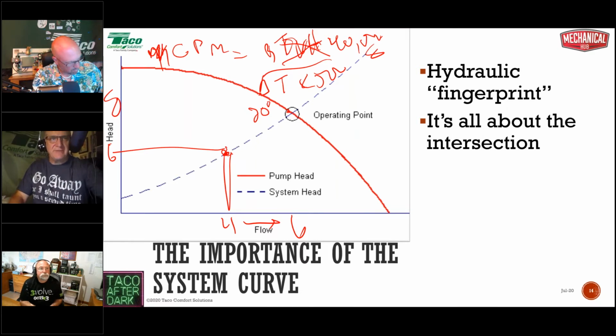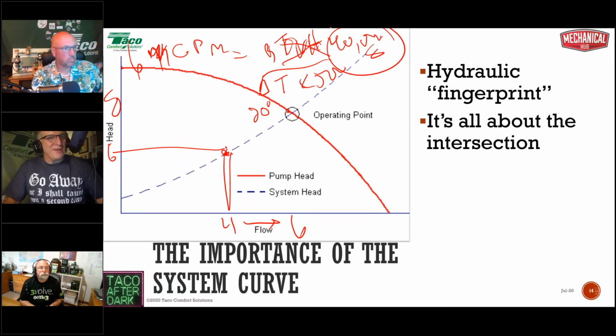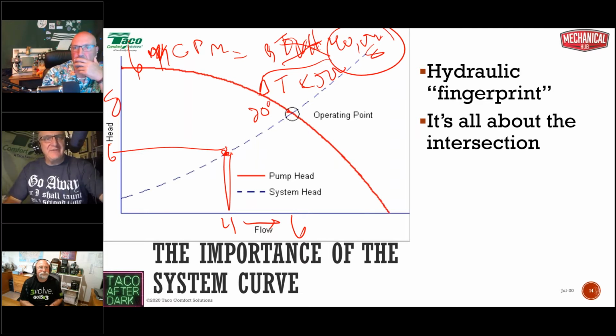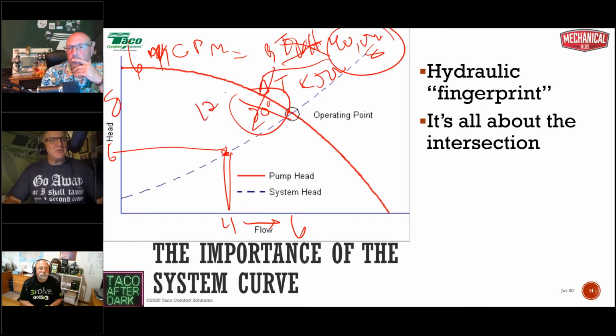I'm not giving it 4 gallons a minute, I'm giving it 6. The BTU doesn't change, so I can deliver more heat, but we don't need more heat. What's going to give is our delta T. Our very best delta T won't be 20, it'll probably be about 12 or 13 degrees. So when the water goes out at 180, it comes back at like 168, or it goes out at 140 and comes back at 128, and we start the whole short cycling dance.